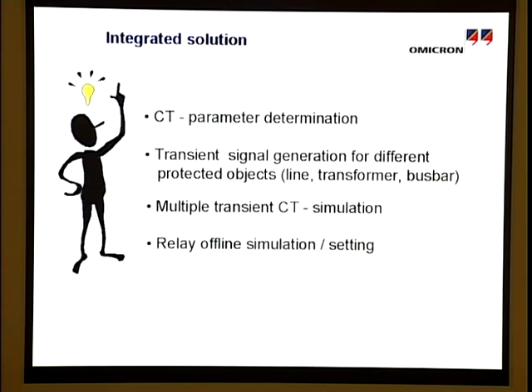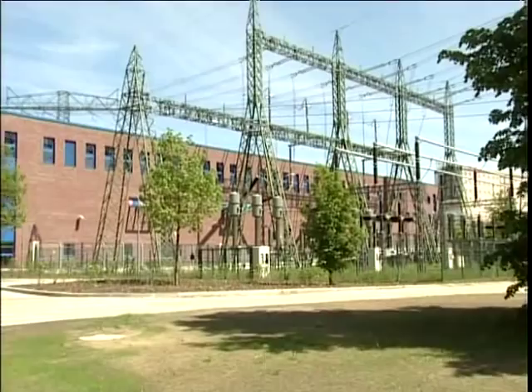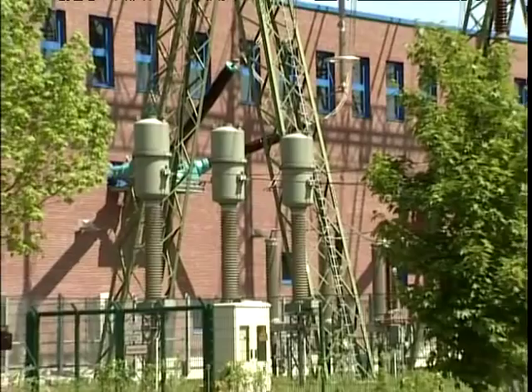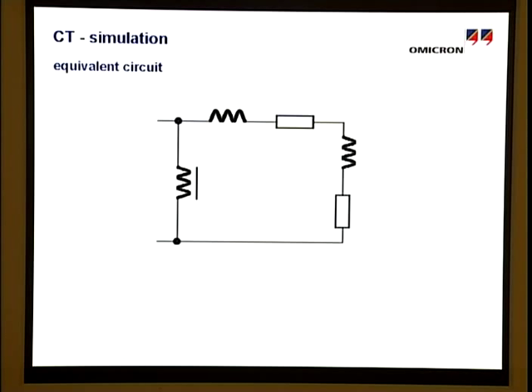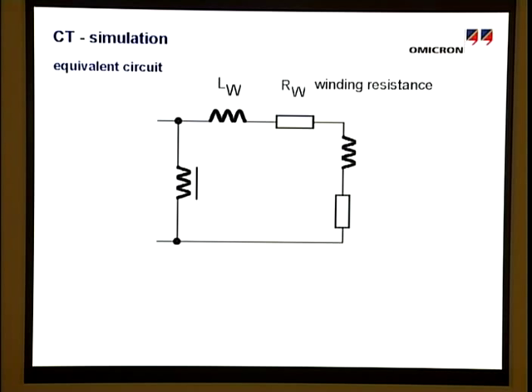In order to form a basis for further discussions, we will first consider the conventional CT in more detail. For the mathematical description of CTs with iron core, the model shown here is normally used. It consists of the leakage inductance, the winding resistance, the connected burden, and the CT inductance.